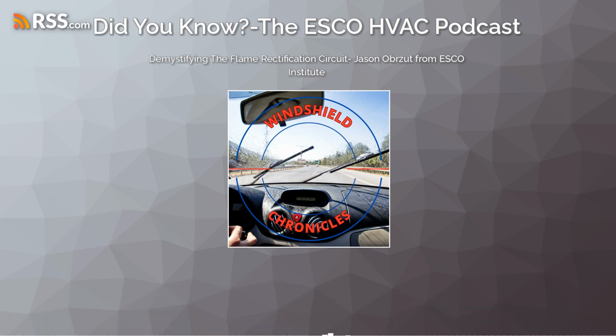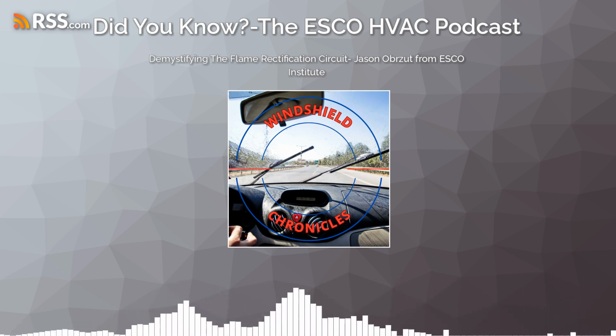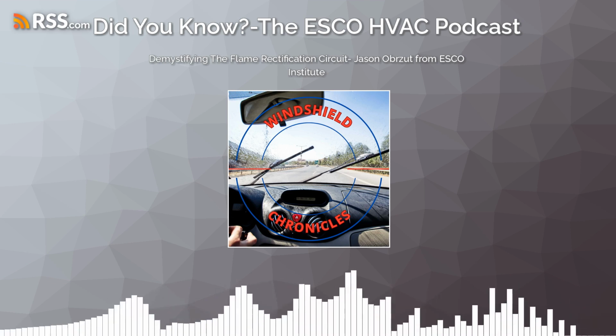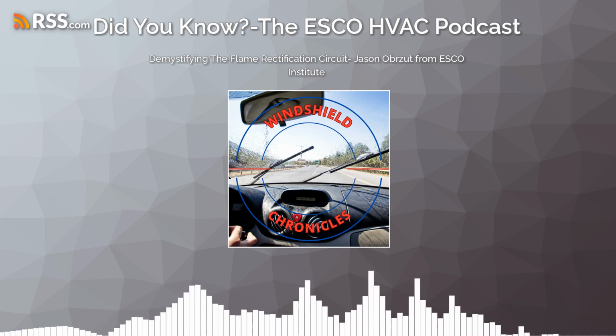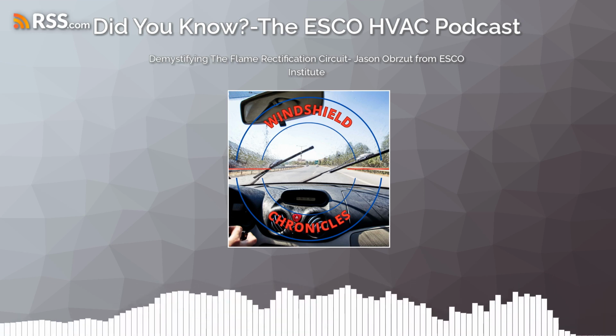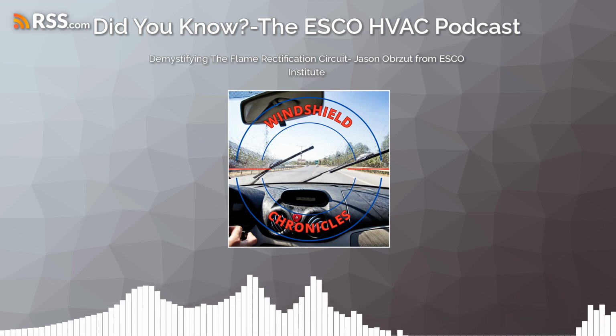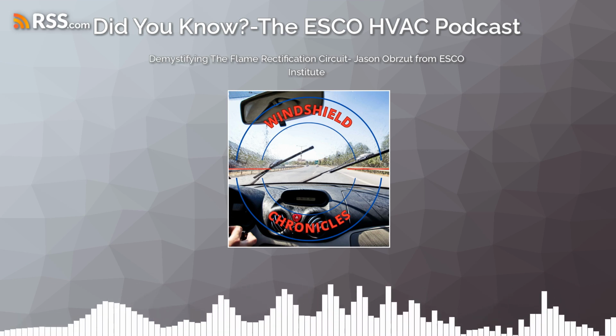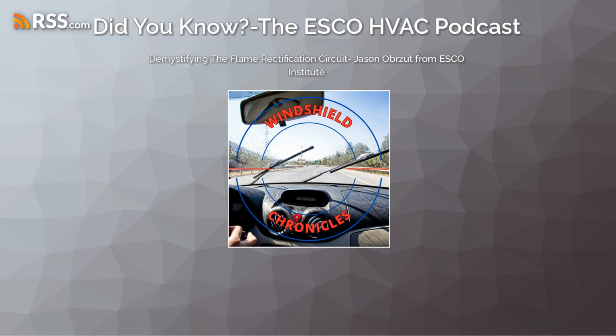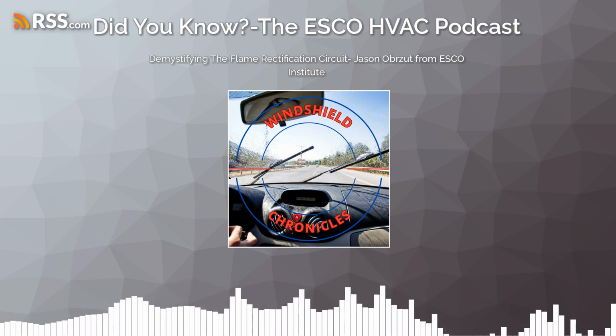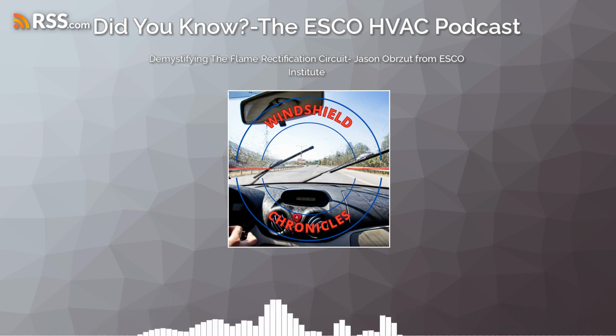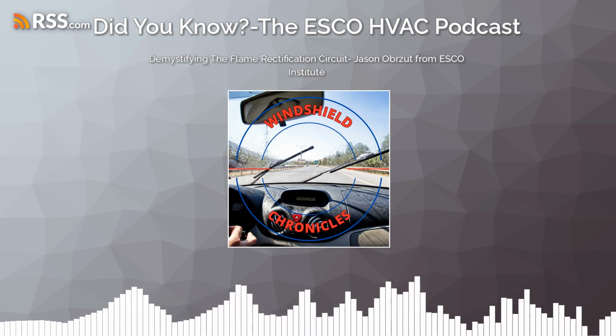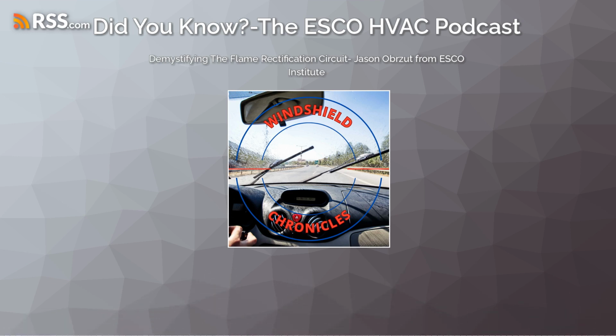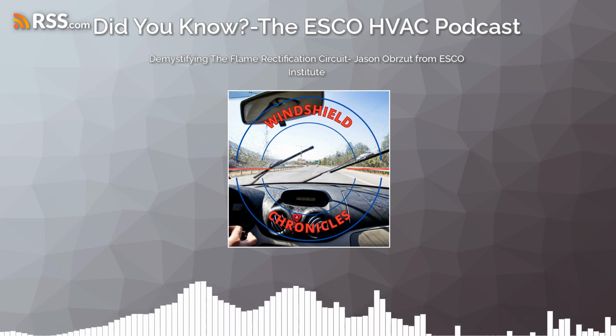And so you'll actually see we are running right now, and my board is as happy as can be. It timed on, brought the flame on, and I'm actually measuring about 1.9 microamps DC. It has 1.9 microamps DC current passing through the flame, creating the electrical circuit that we know as rectification. And that's really it. It's kind of complicated, but a good way to explain this, when you start at that 30,000 foot level, is to say, listen, it's kind of like a switch that closes. That's it. All right. All you're doing is closing a circuit. That flame hits the rod, closes the circuit, and allows current to flow. In the absence of the flame, the circuit is open, no current flows, and we get no ignition, or we get no sequence.